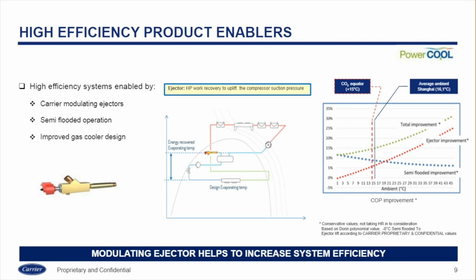Based on the experiment data we have from the field and the test data, the energy efficiency improvement for this modulating ejector combined with the semi-flooded evaporator is about 17%. Here I take Shanghai, for example. This is from China. But if we consider Southeast Asian countries, like the Philippines, Singapore or Malaysia, the ambient temperature is much higher, so we can gain more efficiency improvement. For example, if the ambient temperature is 30 degrees, then the total energy efficiency improvement can be up to 20%. That is a significant energy saving for a big industry application. Okay, so that's the first one, the high efficiency enabler. Next page, please.